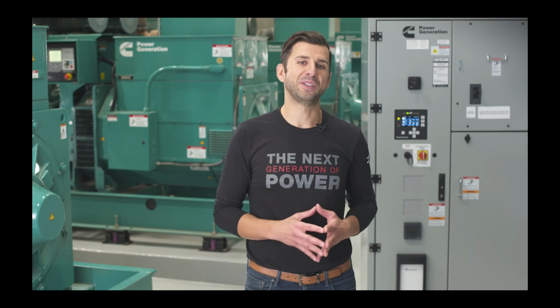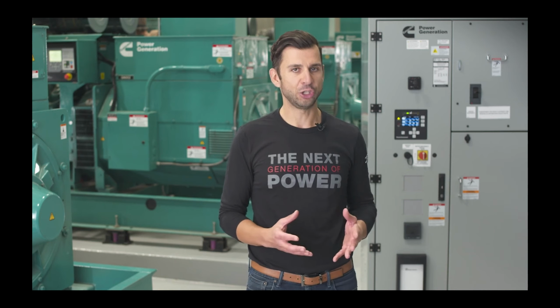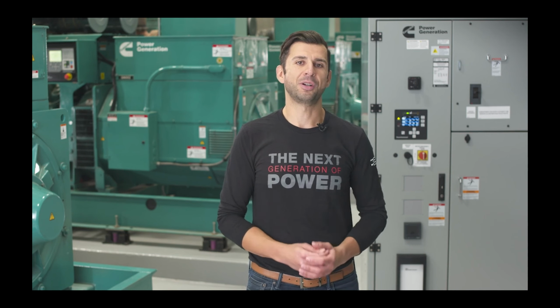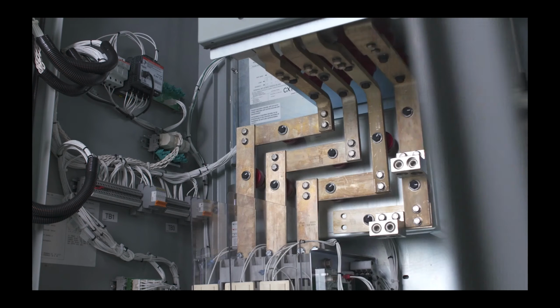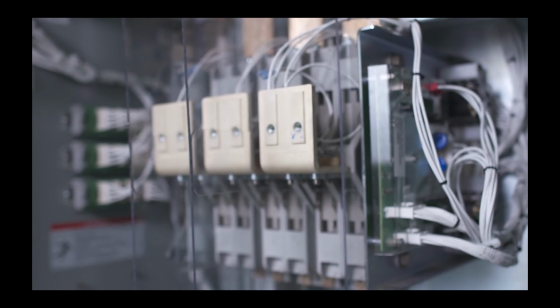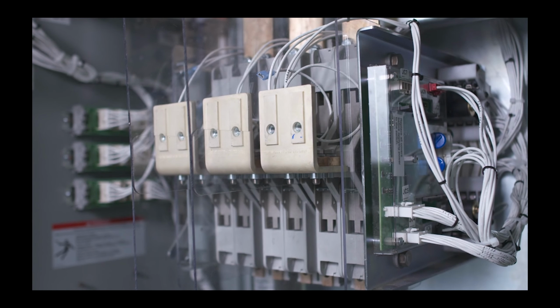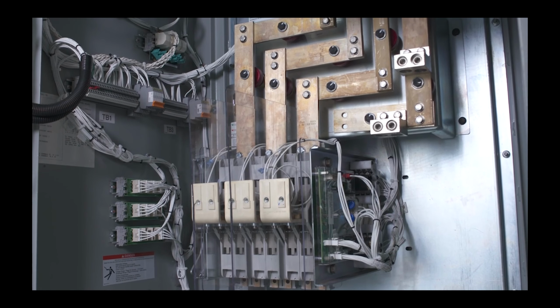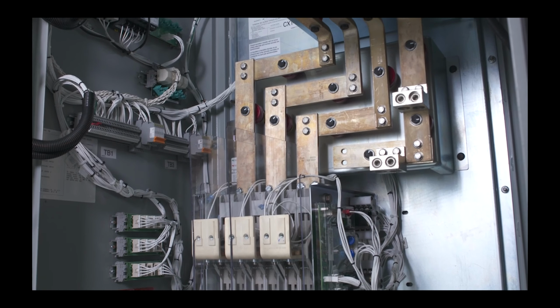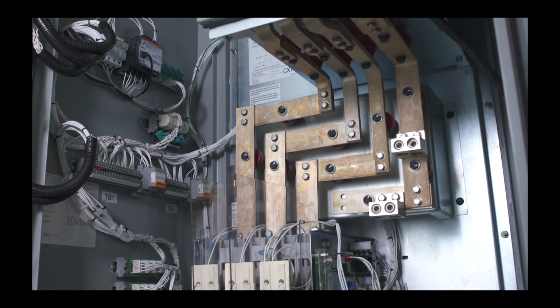The typical components of a transfer switch are the mechanism, control, accessories, and an enclosure. The heart of the Power Command X series transfer switches is the Cummins innovative high-endurance mechanism. This simplified design reduces multiple failure points and enhances product reliability and serviceability. The high-endurance mechanism with the blow-on technology is designed to minimize contact damage during a fault condition, therefore retaining its full capability to carry up to 100% of its rated load.